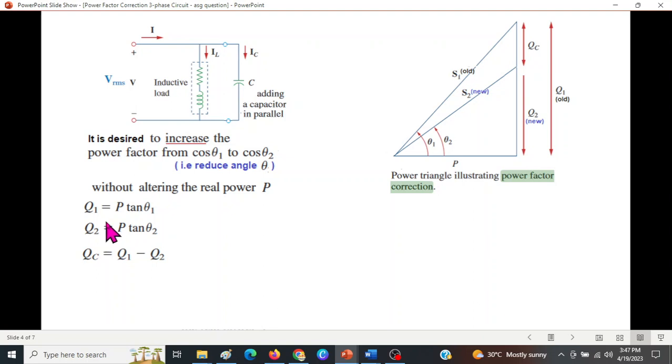From here you can see that Q₁, this one, is P tan θ₁. We know the tangent formula is perpendicular over base. So this is perpendicular, this is base. Q₁ over base P is tan θ. Similarly Q₂ is P tan θ₂, and for the reduction by the capacitor, Qc or the Q by capacitor is Q₁ minus Q₂.